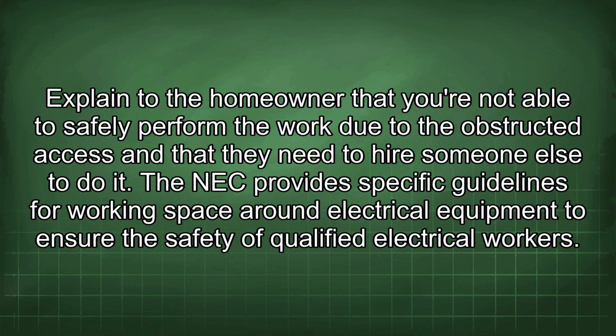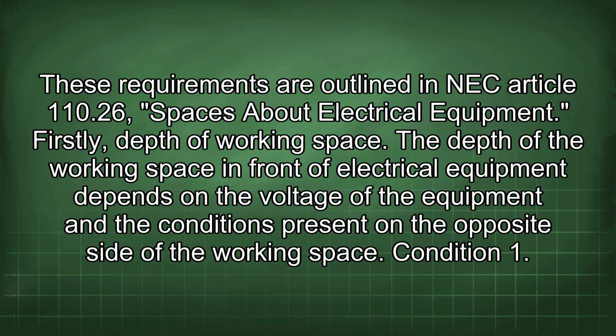The NEC provides specific guidelines for working space around electrical equipment to ensure the safety of qualified electrical workers. These requirements are outlined in NEC Article 110.26, Spaces About Electrical Equipment. Firstly, depth of working space. The depth of the working space in front of electrical equipment depends on the voltage of the equipment and the conditions present on the opposite side of the working space.